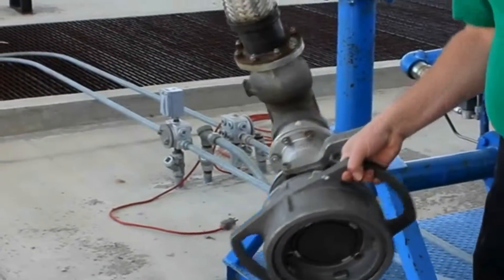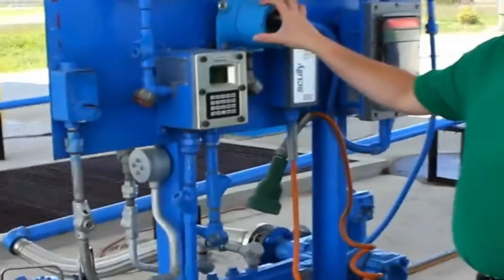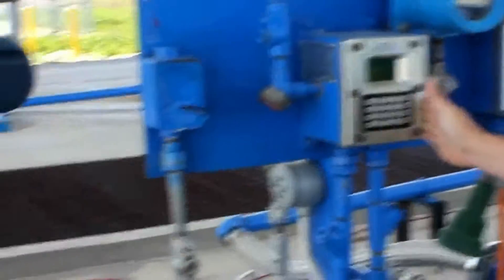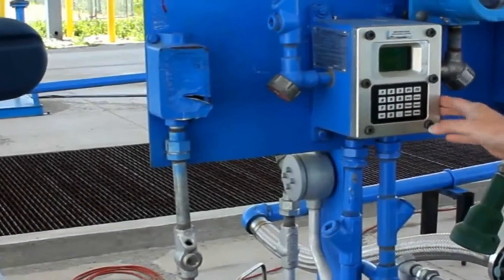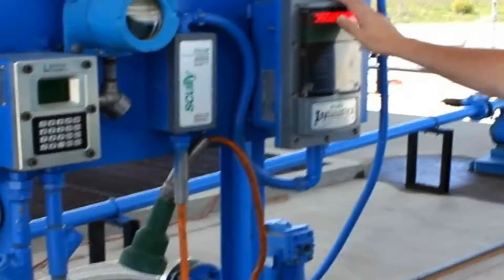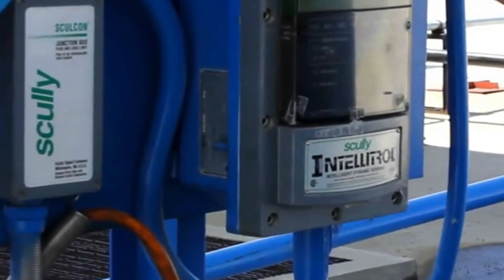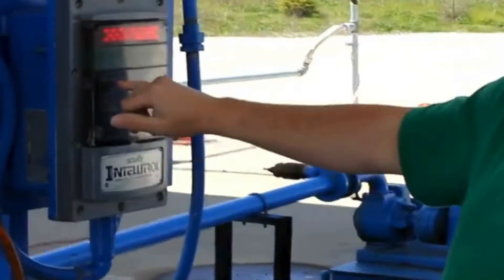Right here you've got your load head — this is fully graded truck capability, 6-inch load head. We have a proximity reader for a card, and keypad entry so you can enter in specific accounts. It does come equipped with the Scully overfill protection, both optic and ground. We currently use the Scully ground system; we don't use the individual compartment Scullys.